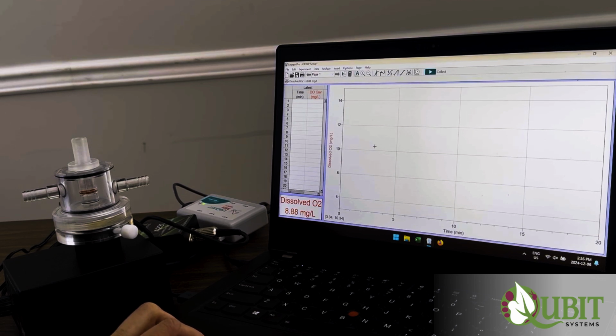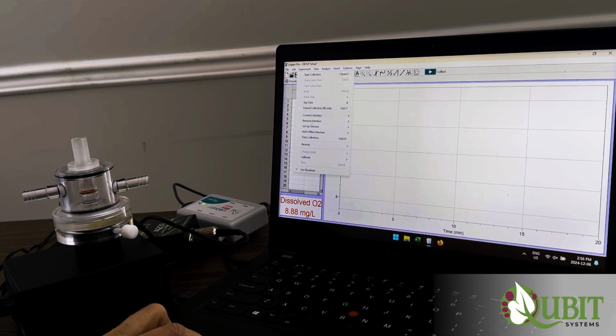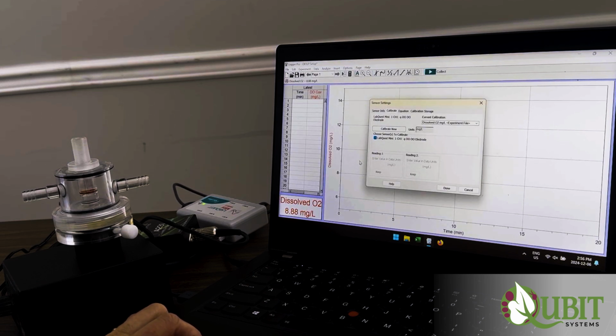And to calibrate the oxygen electrode, right now I've got air saturated water inside the electrode. You go to experiment, calibrate, select the DO electrode, and you'll see the sensor settings window. Ensure first that under calibration storage, you have experiment file selected, and under current calibration, you have experiment file selected. So this new calibration will be saved with this experiment file. You then select the Calibrate tab here and go to Calibrate Now.